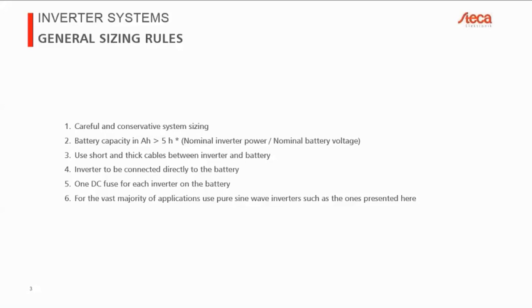So especially for inverters, because inverters are always quite inviting for customers to add additional loads, which maybe you didn't know about when you were designing the system. So here it's that much more important to have a careful and conservative system sizing. In other words, when in doubt, increase the PV array, increase the battery capacity to make sure that you can really serve those loads reliably.